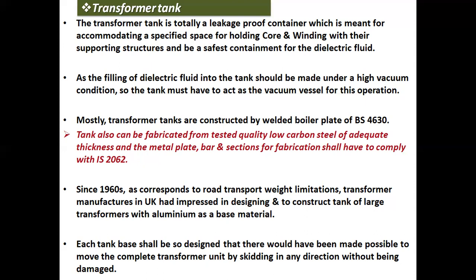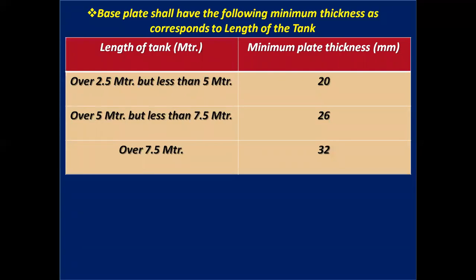Each tank base shall be designed so that it is possible to move the complete transformer unit by skidding in any direction without being damaged. The base plate shall have the following minimum thickness corresponding to the length of the tank. For a length over 2.5 meters but less than 5 meters, the minimum plate thickness should be 20 millimeters. Over 5 meters but less than 7.5 meters, 26 millimeters thickness. Over 7.5 meters, the minimum thickness will be 32 millimeters.